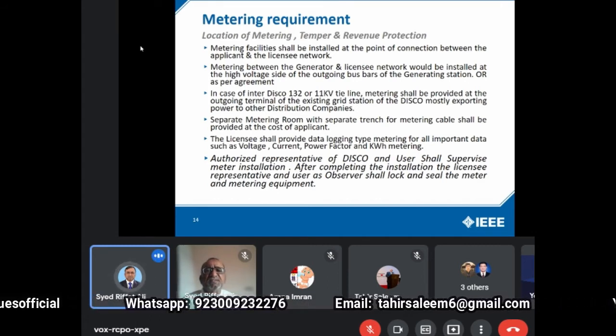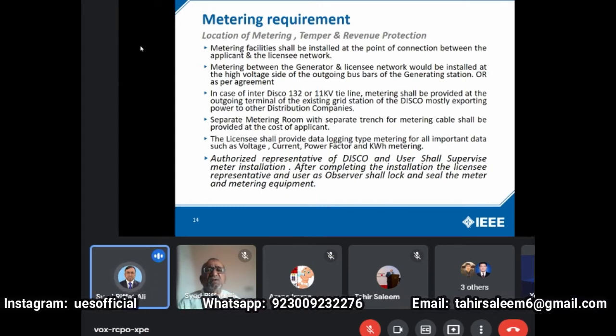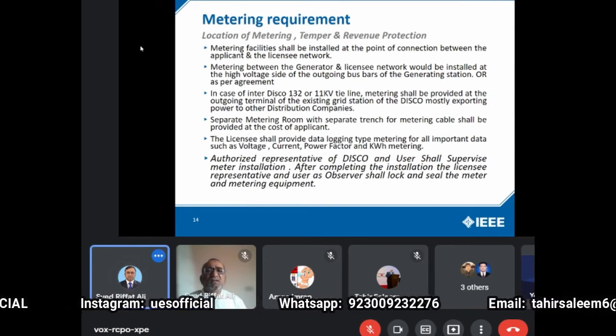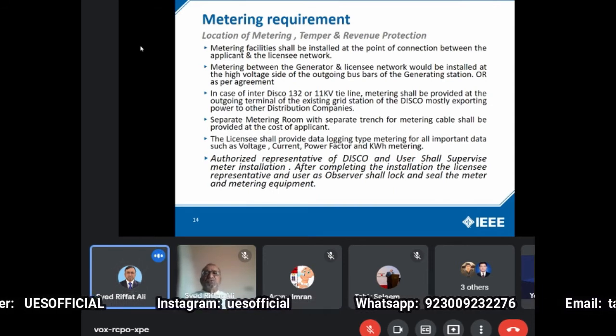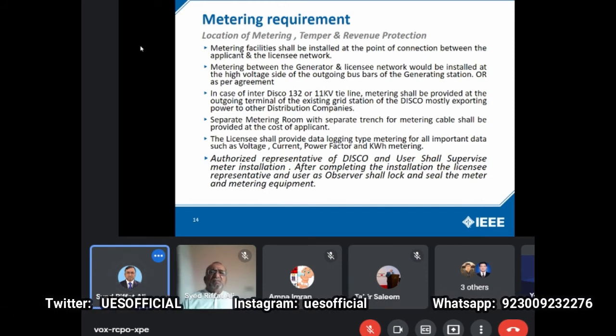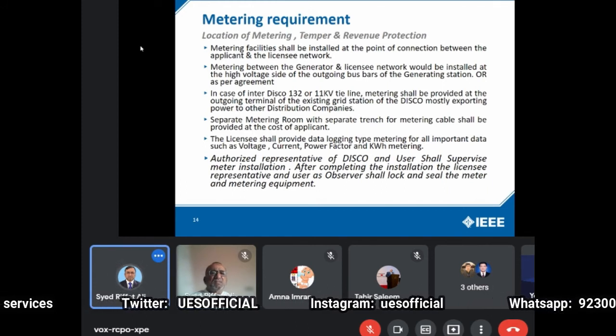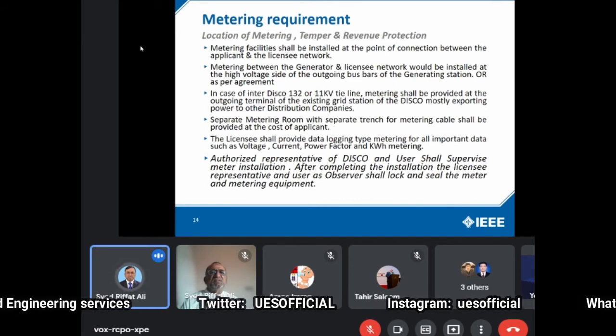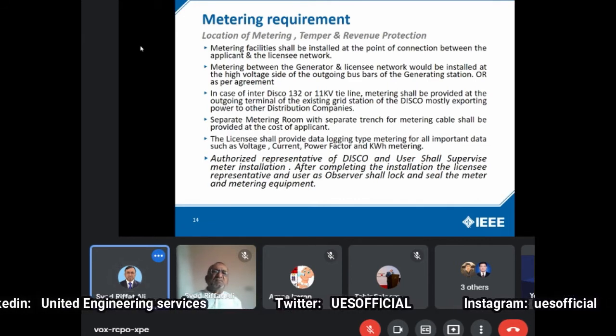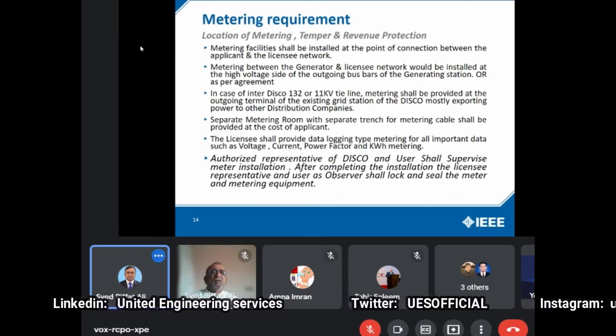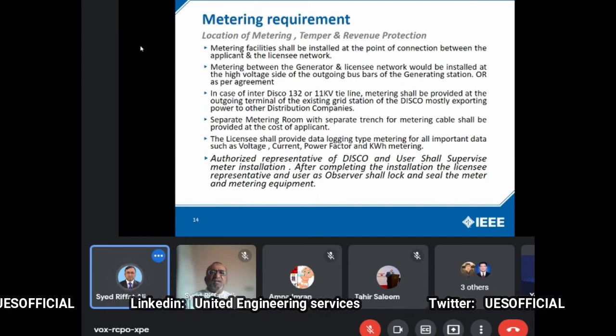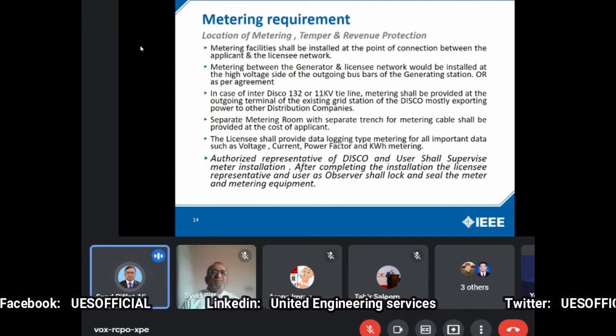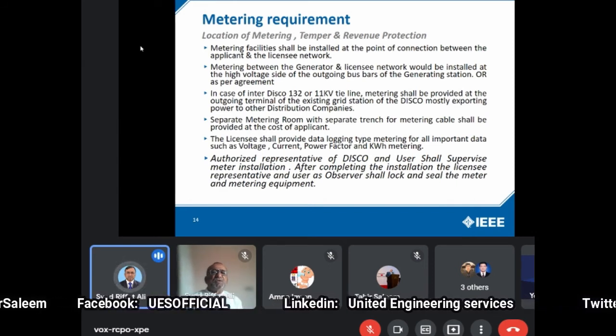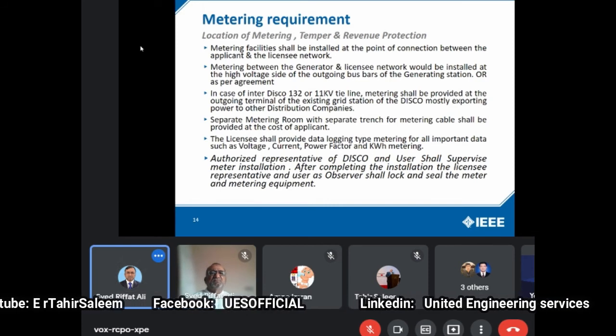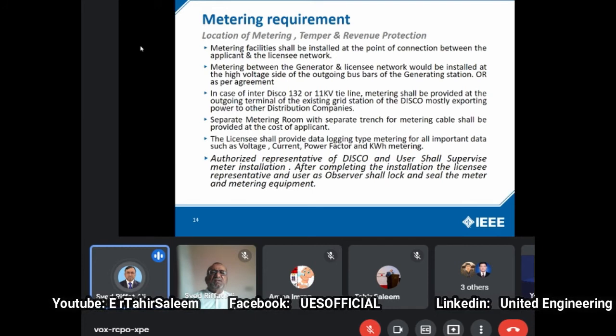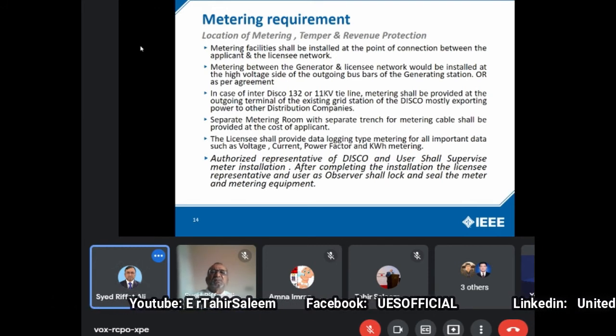Metering between the generator and the licensee network would be installed at the high voltage side of the outgoing busbar of the generating station. This is what is specified in the sub-distribution code. But there is also a provision that the seller and the buyer may agree on some other location, but it should be incorporated into the said agreement between the two parties. In case of an interdisco 132 or 11 kV tie line, metering shall be provided at the outgoing terminal of the existing grid station of the disco, mostly exporting power to the distribution companies. The location has already been specified at the distribution grid station of the distribution company.